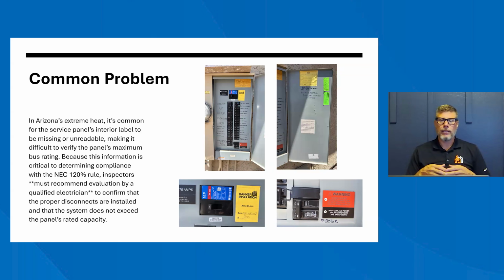You'll also want to make sure that you're documenting any conditions with the panel that you normally would. So if you're doing a solar inspection only, you get called out, hey, can you do this solar array inspection for me? I need to have a warranty and review on it. Yeah, we can do that. You're going to do an inspection on that panel just as you would any other panel at any other time on any other inspection. So you want to make sure that you're going through it and doing your standard electrical inspection for that panel. Remember, you're not citing code on this. You're always going to recommend a licensed electrical contractor for the panel. Not verifying code, just what's potentially wrong.